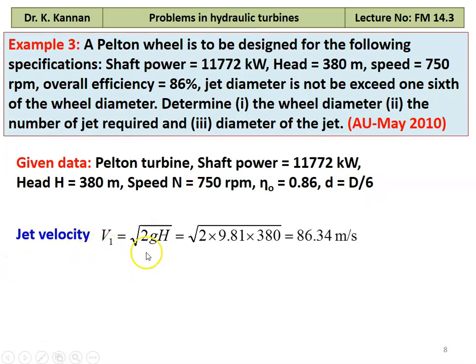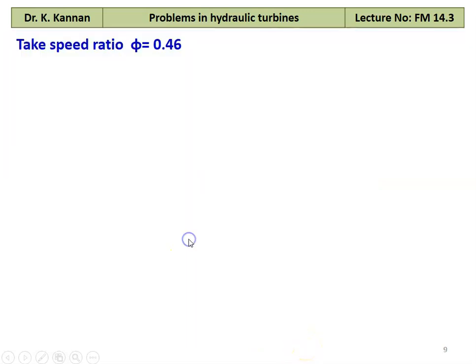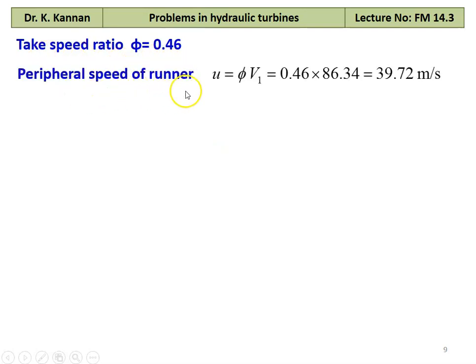Jet velocity V1 = √(2GH) = √(2 × 9.81 × 380) = 86.34 m/s. Total flow rate Q = shaft power / (ρGH × overall efficiency) = 11772 × 10³ / (1000 × 9.81 × 380 × 0.86) = 3.67 m³/s. Assuming speed ratio φ = 0.46, peripheral speed U = 0.46 × 86.34 = 39.72 m/s.